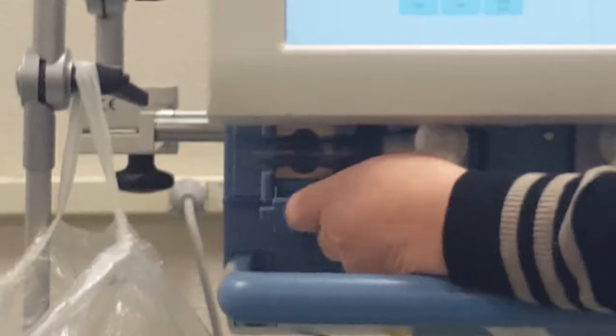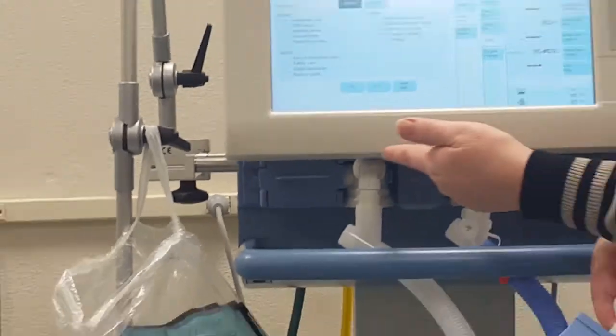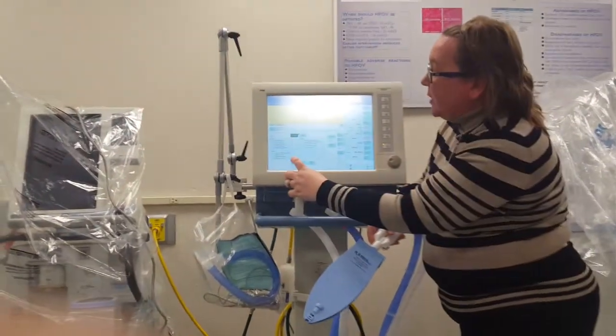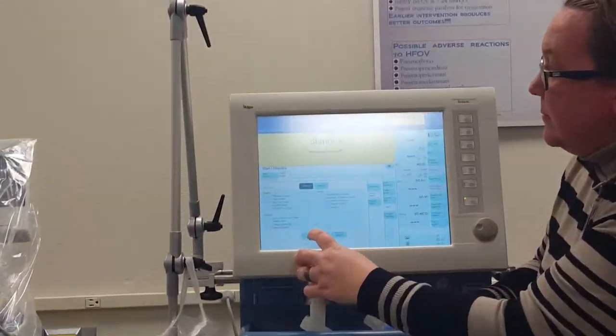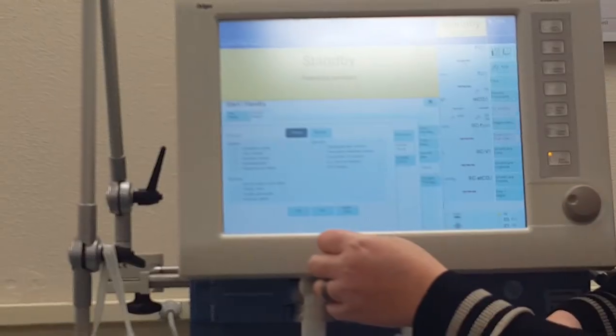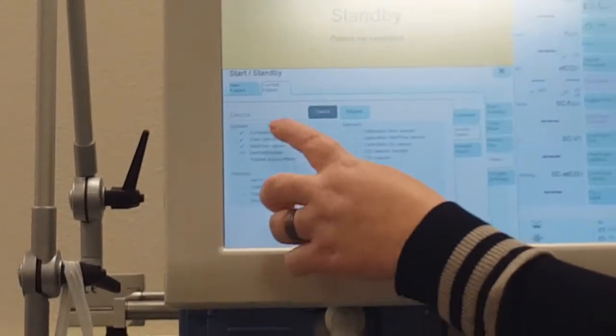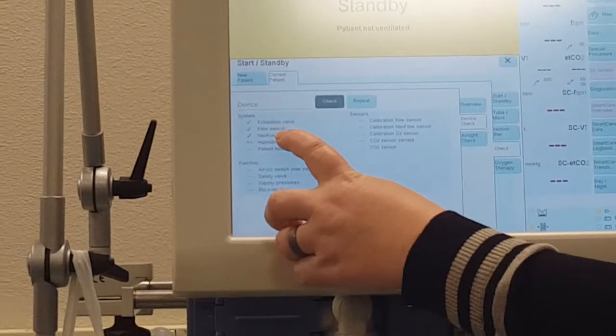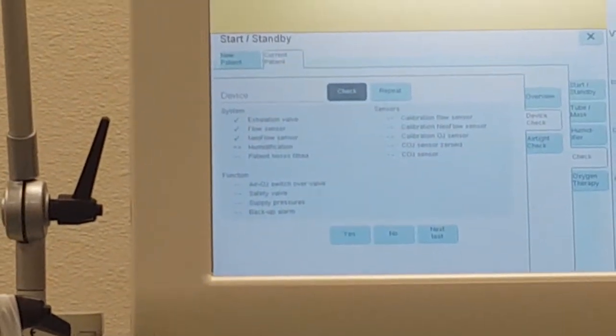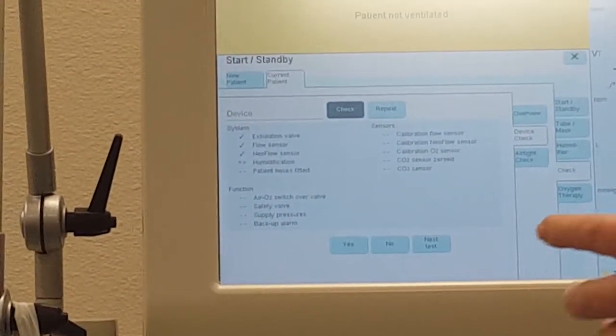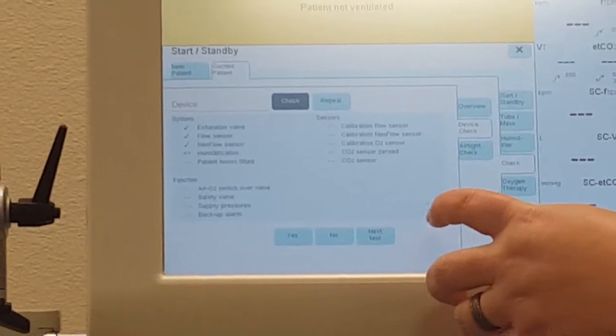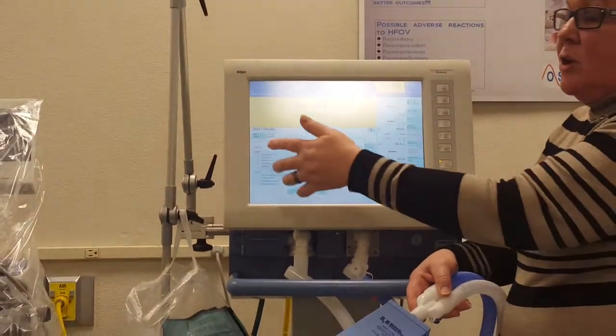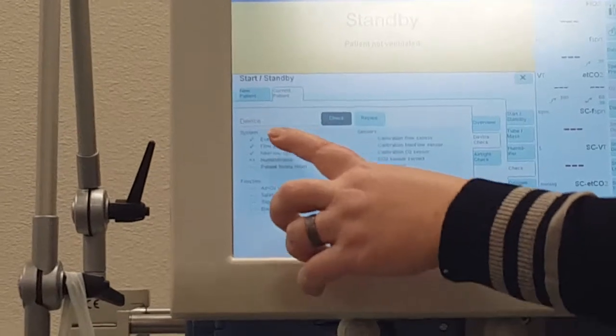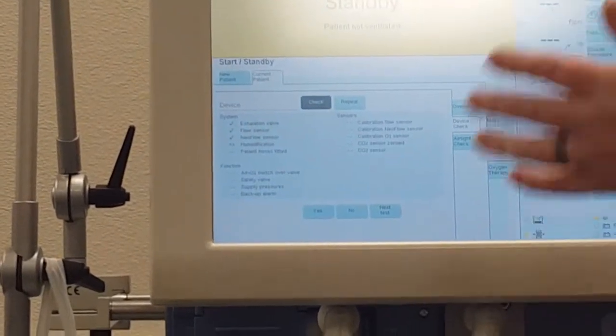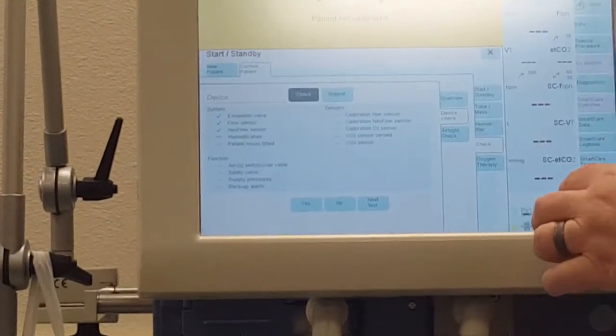So you just want to make sure everything's in. But if it's ever telling you to check it, that's where you have to go. So we're going to check that and hit yes. I accidentally hit the wrong button, but the next test was neo flow sensor. This is not a neonatal, so you should hit next test and bypass that one. There are two different ones that say neo while you're doing the calibration. Whenever you see the word neo, hit next test.